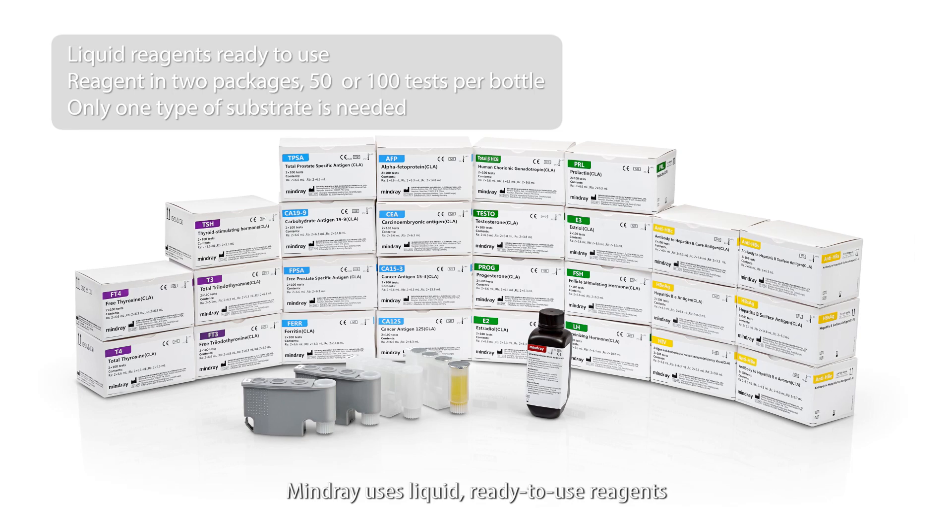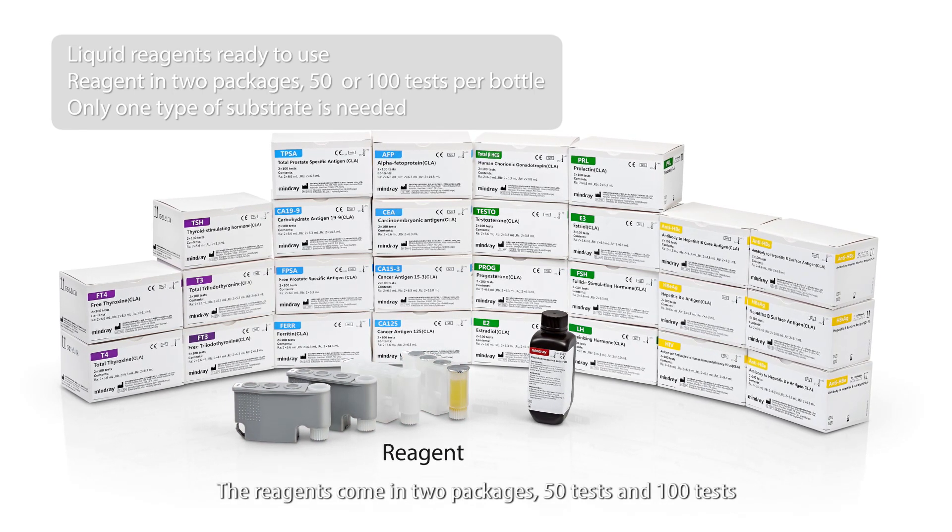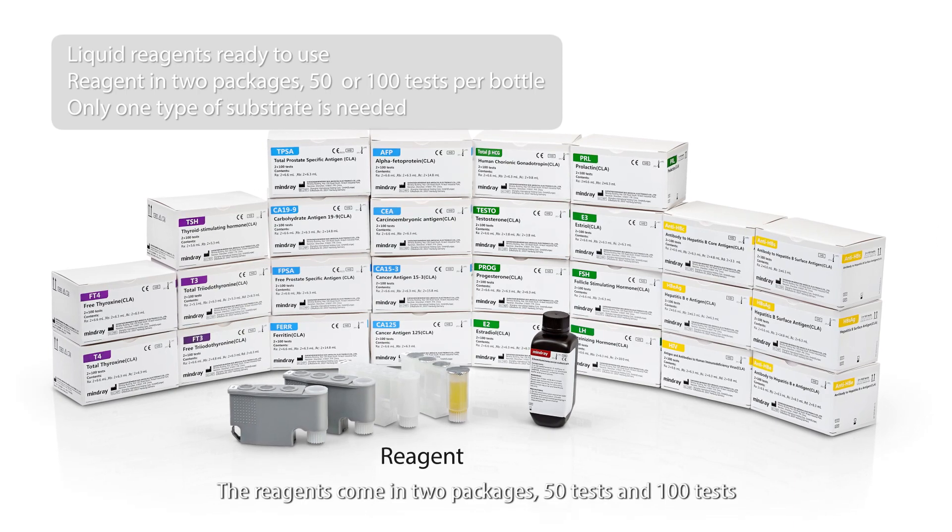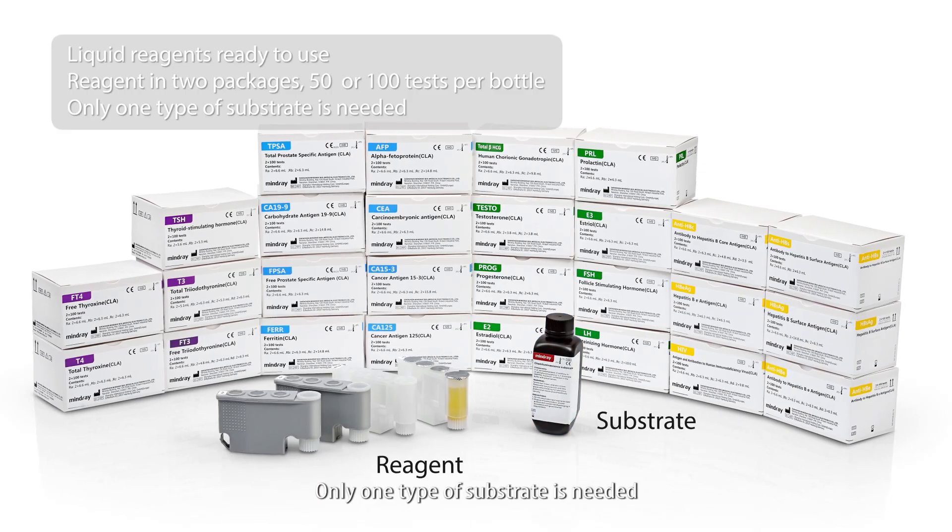MindRay uses liquid, ready-to-use reagents. The reagents come in two packages, 50 tests and 100 tests, to suit customers with different requirements. Only one type of substrate is needed.